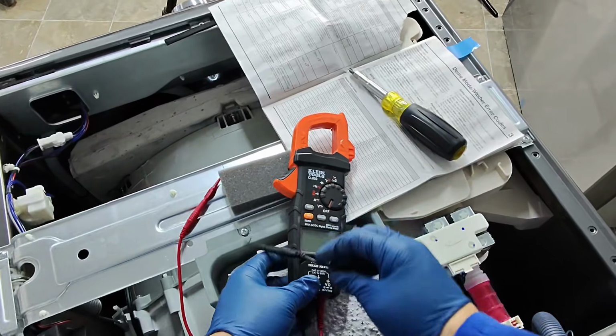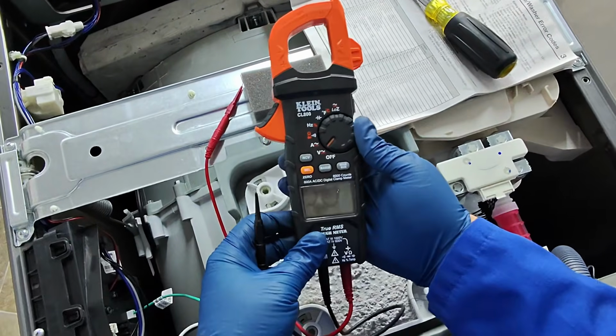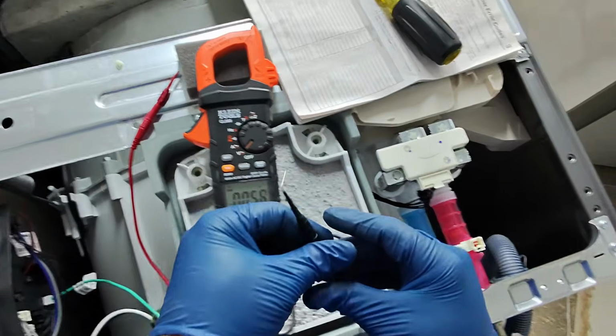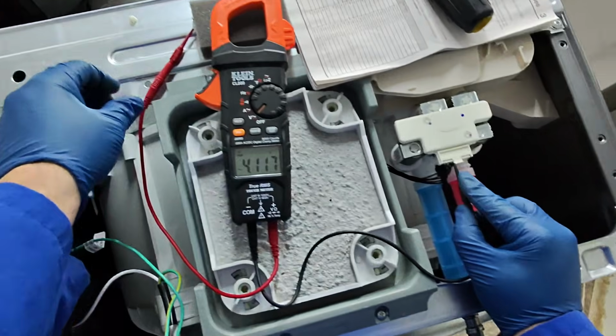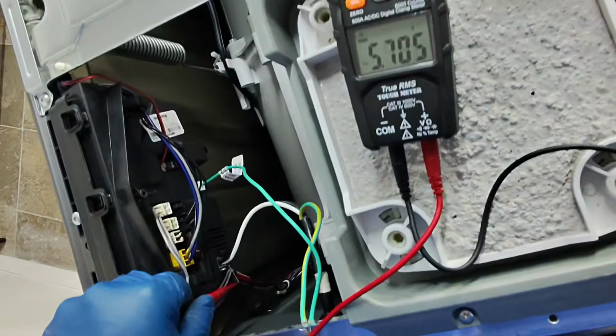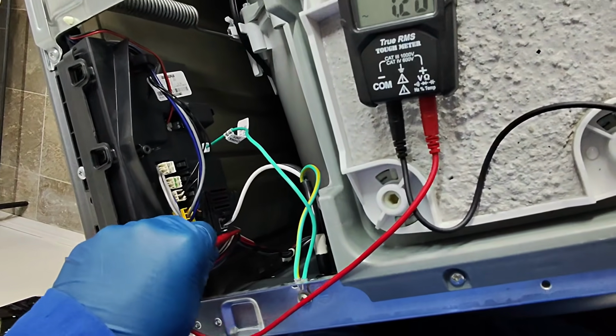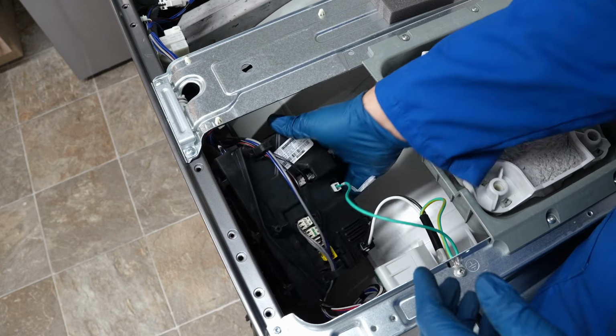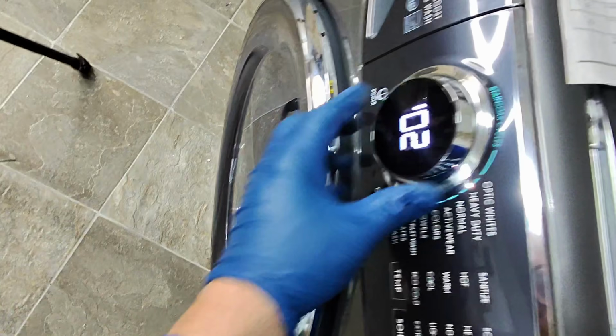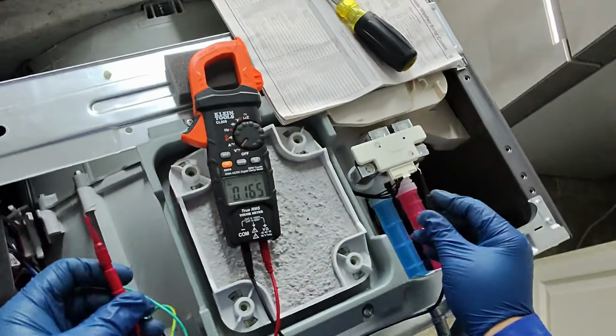Take a multimeter and set it to voltage AC. You'll see at the tips of each of the probes, I have a set of what's called back probes. I bought them from Harbor Freight, but there may be multiple places you can buy these very thin leads. From here, locate the white neutral wire that comes in from the power plug at the wall that plugs into the board. It's white and it's located here at J1-2. Install 1 probe to this wire, then rotate the dial knob at the front of the unit from any of the diagnostic modes, number 1 through number 8, like we were trying to force the valves on.